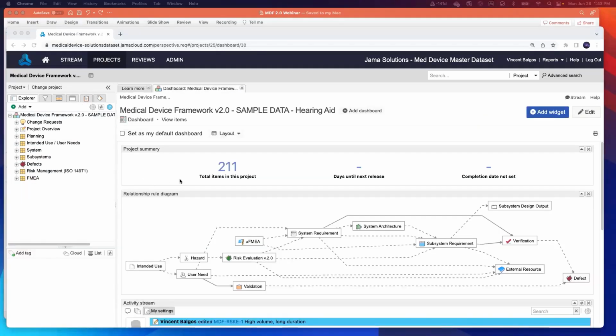The next item that I'd like to talk about is this new feature called the Risk Lookup Matrix. Available in 8.75.4, this feature allows a new lookup matrix risk analysis approach that automatically outputs the desired content based on a pre-configured lookup table. This really aligns with 14971.